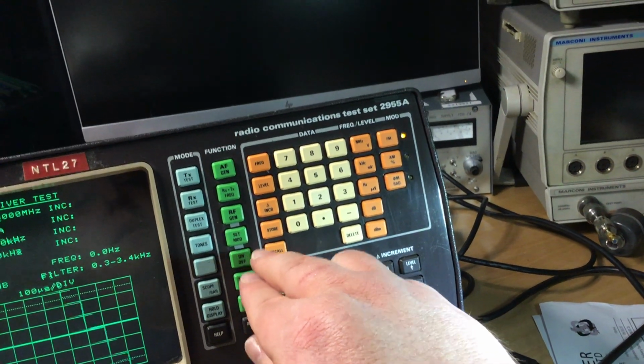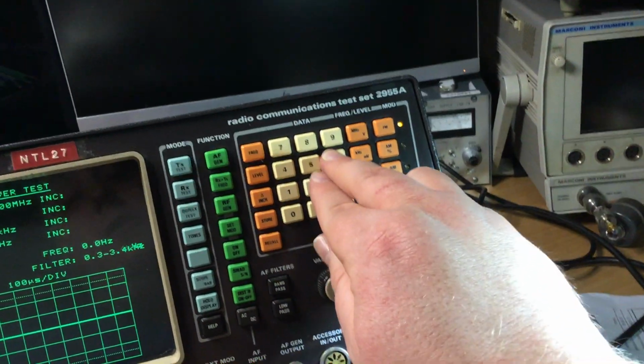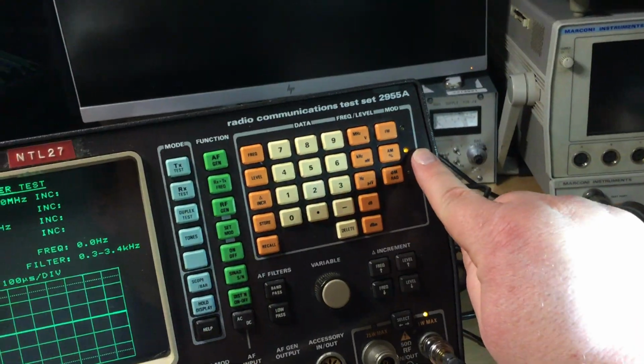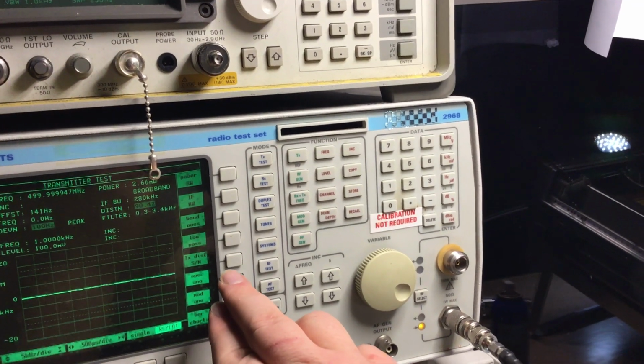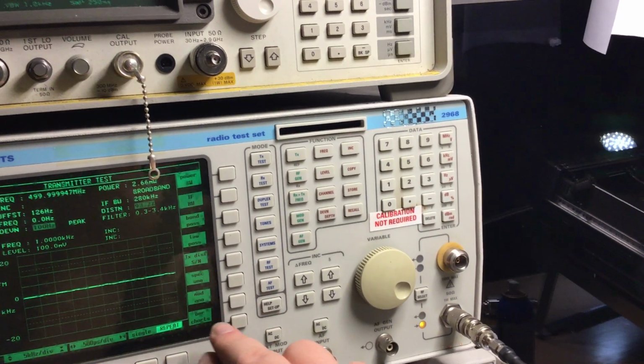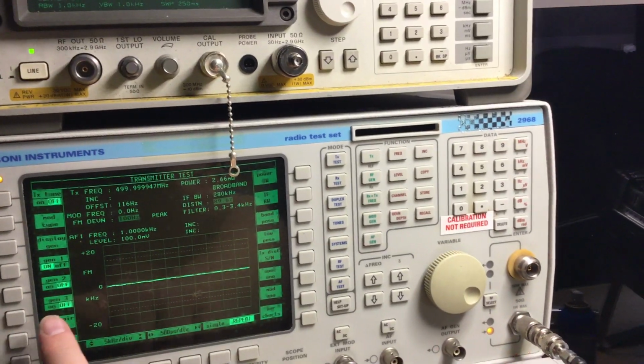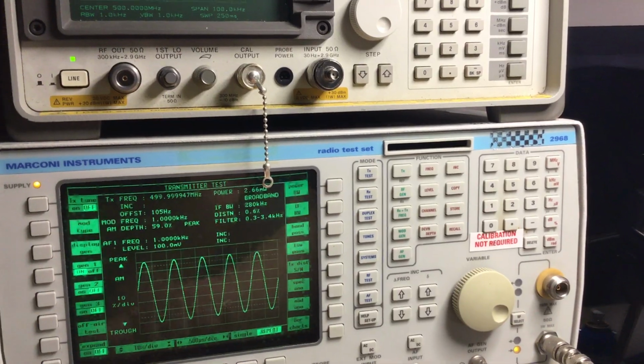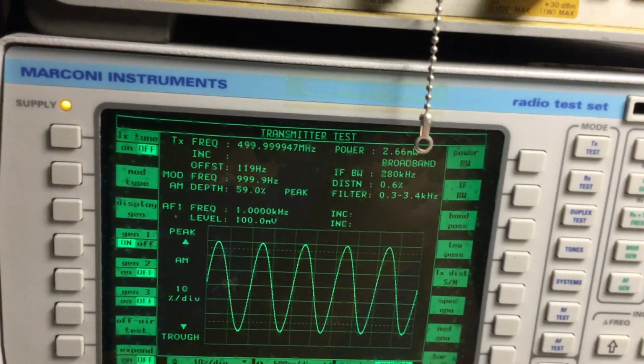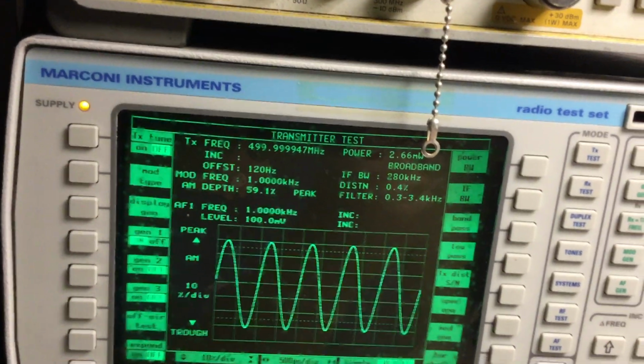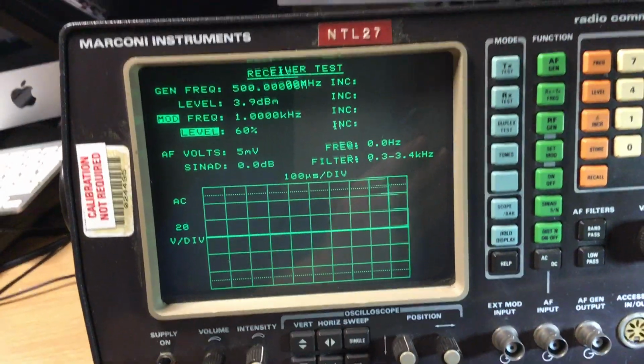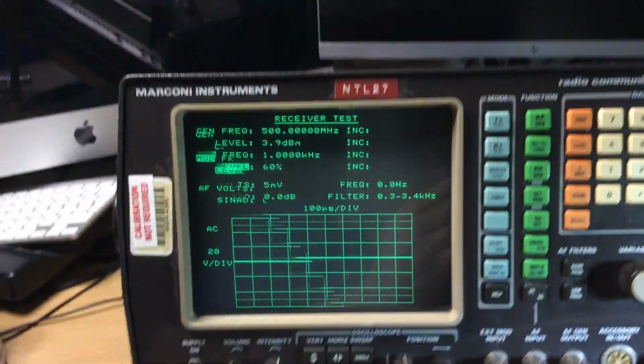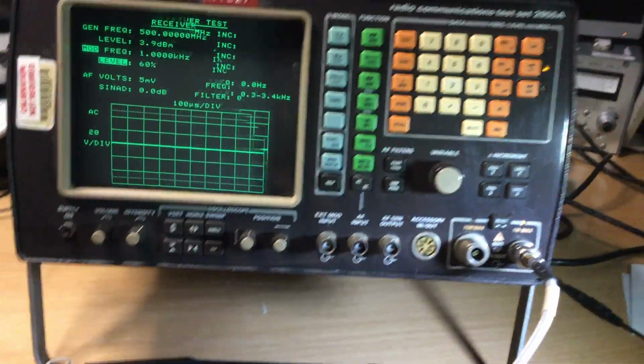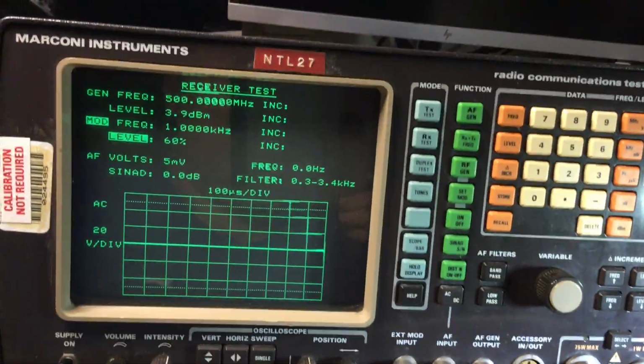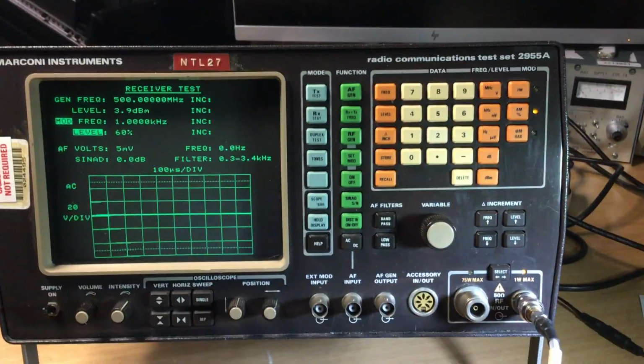So we could say set mod level 60%, and now it changes to AM. And then if we do the same on here, we can set whether or not that's AM or FM. We can find out how to do that on this, because it's been a while. Mod type, there we are, and that's now reading 59%, so it's spot on. You know, it's very, very close to 60% mod there. And that gives you a little rundown of just some of the things that you can check and test when you're doing your own calibrations or whatever.